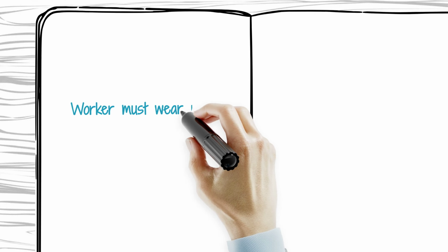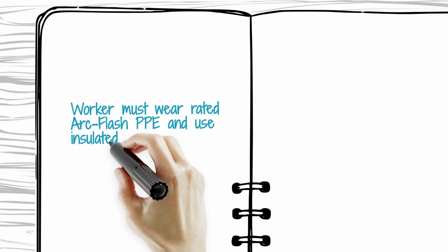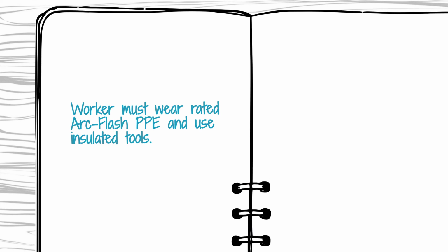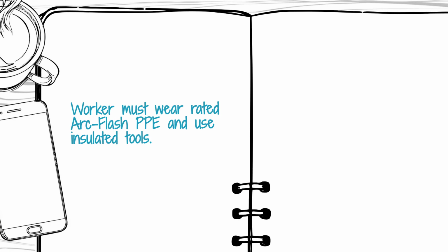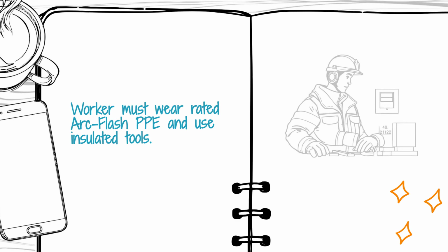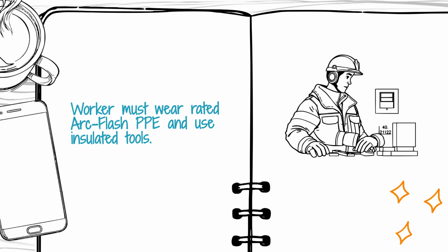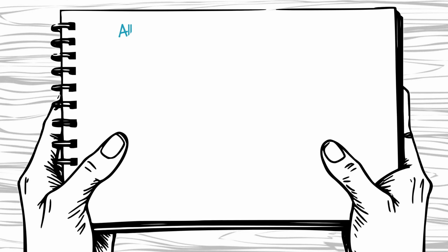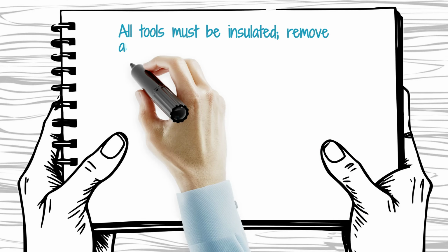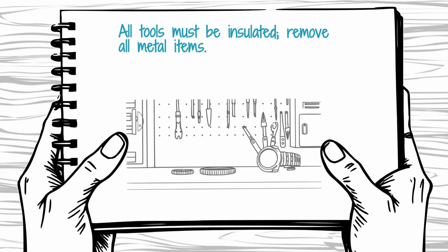The third step is personal protective equipment, PPE. Standard gloves are insufficient. The worker must wear full rated arc flash PPE. This includes a multi-layered flame-resistant suit, an insulated helmet with a full-face shield rated for the calculated incident energy, and high-voltage insulating gloves with leather protectors. All tools used must be insulated and rated for the voltage present. Jewelry, metal watches, and any conductive materials must be removed.